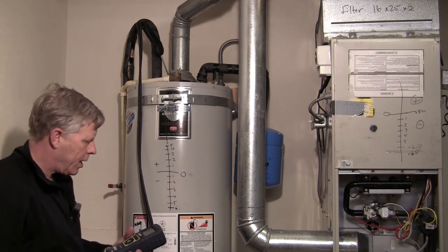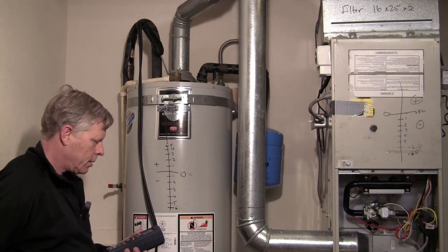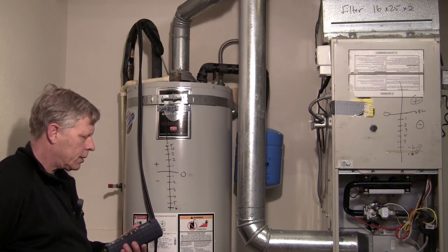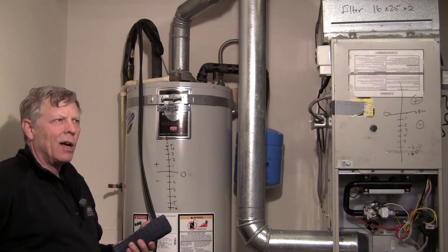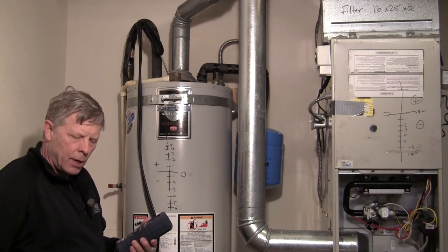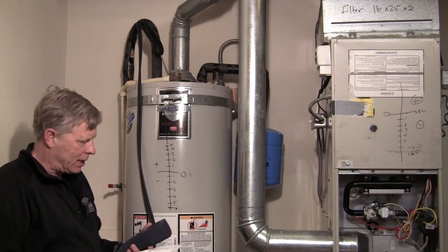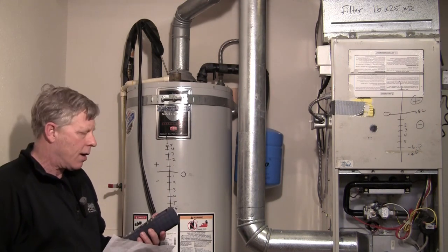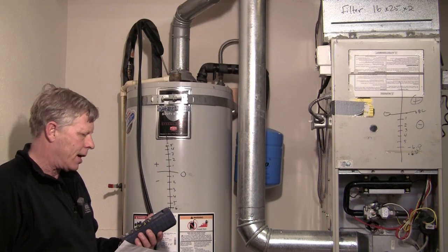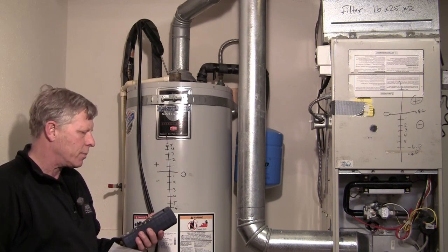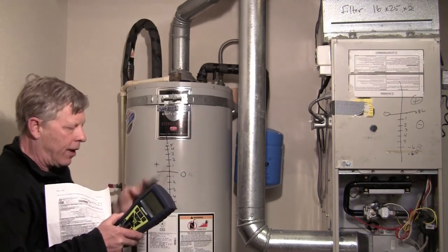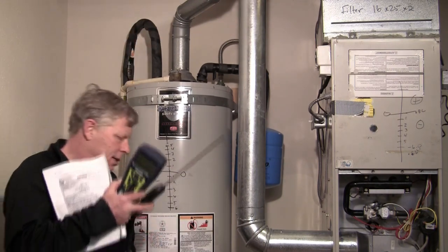Our CO air free is going up. It's in the 30s. It's in the 40s. If you check on the back of the form, page 2 of the form, it says we can be as high as 200 parts per million CO air free, and it's leveling off right now at about 47 parts per million. Okay, so that's good. It fails spillage and it passes the CO at this point.